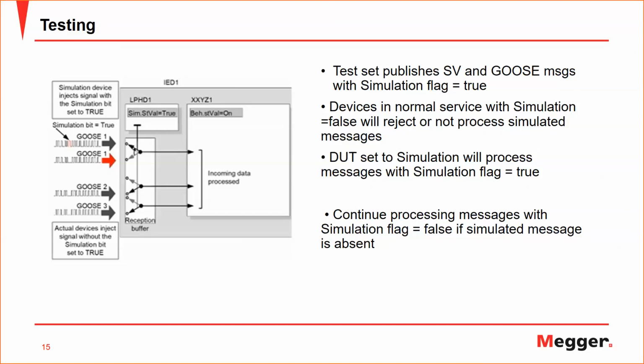All right. So when you want to do testing for an IED with sampled values and even GOOSE messages, you will set your test equipment to publish these sampled value and GOOSE messages with a simulation flag set to true or 1. Now, if a device is in normal service mode with the simulation flag being false, it will not accept these simulated messages. Even if it's subscribed to them, it will not process them at all. So once you put your device under test, or just a slice of it, the logical node, in test mode or simulation flag, it will start processing these messages and outputting simulated flagged outputs as well.